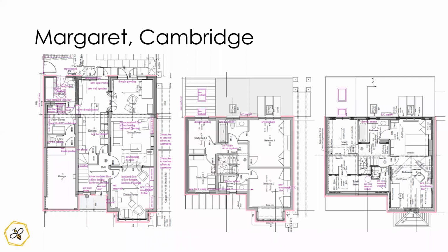Okay, well, I've got a question actually about the 70 watts per square metre. To me, that's where I would start, is to say that sounds as though somebody's plucked it out of the air. It needs a proper heat loss survey, as we've discussed earlier.